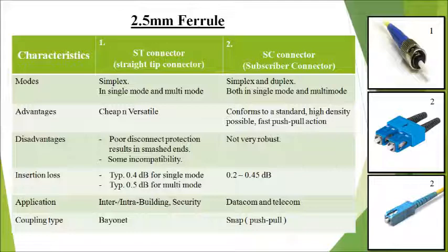Typically 0.4 dB for single mode and typically 0.5 dB for multi-mode for the insertion loss of ST connector. ST connector have been widely used in inter or intra-building application and also for security application. ST connector use bayonet type of coupling.